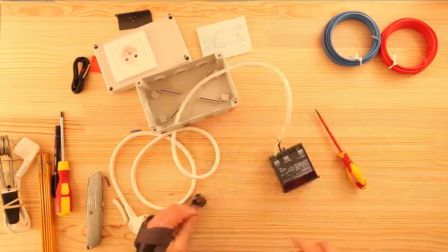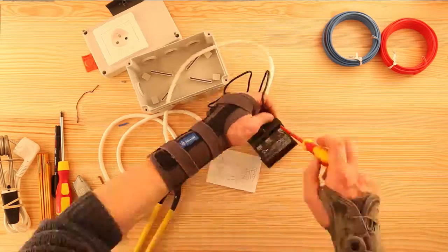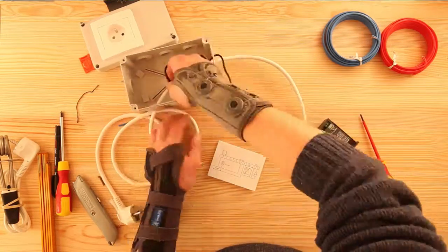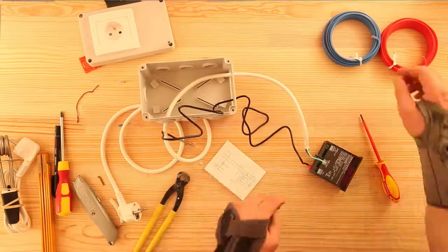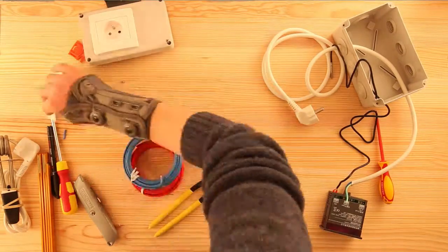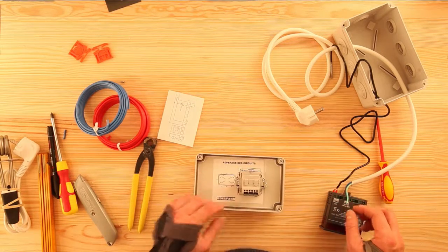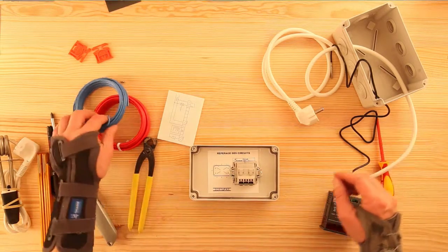Regarding the wiring, it's quite simple. I just follow the wiring diagram that comes with the controller. The NTC label refers to the thermistor sensor. Regarding the wires through which the current of the heater will pass, one needs to choose wires with a fair cross-section, in order to avoid overheating inside the junction box, due to undersized wires for the load. For reference, P equals U times I.